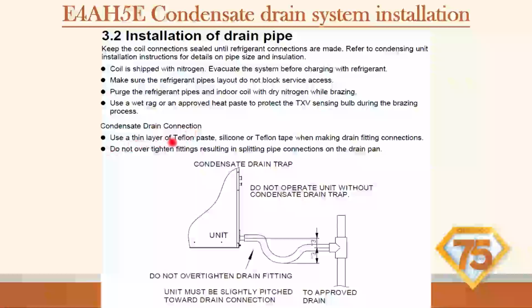Condensate drain connection: use a thin layer of Teflon paste, silicone, or Teflon tape when making the drain fittings. I always like using Teflon tape. Do not over tighten. You can split that pipe connection. I've been guilty of it myself. Over tightening it, and it's just plastic, so you can split it or ruin your threads inside your 3/4 inch MIP PVC adapter. Do not over tighten. I had one guy working for me too that just would use pipe wrenches on that. I was like, oh, Sean, you gotta stop doing that.